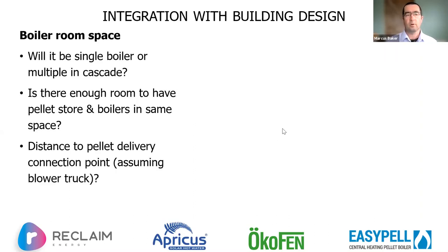So in terms of boiler room space, last week we looked at how you can deliver pellet fuel systems, and that tends to be up to about 200 kilowatts, more or less 250 maybe at the most, are the biggest off-the-shelf pellet boilers before you start getting up into half or maybe multi-megawatt custom-made ones. But for the standard commercial offering, we're going to be cascading multiples of smaller ones. And so thinking about how we lay it out, the nice thing about a cascade is that you can dot them around a bit more. You can be more flexible about that placement. It doesn't just have to be one hulking unit in a specific spot. Ideally, we'd have the pellet store and the boilers in the same space, but it's not absolute, and we'll go into that. And the distance to the pellet delivery connection point.